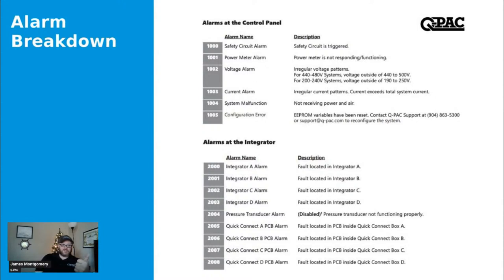The next one is 2004, a pressure transducer alarm. You'll see it says disabled. Remember I told you when you were running the unit, you ramped it up and potentially it took a while for you to see CFM. This was a pretty common thing that was happening. We were throwing an alarm saying the pressure transducer wasn't working. So this has been disabled. Maybe for future use, we'll add it back.